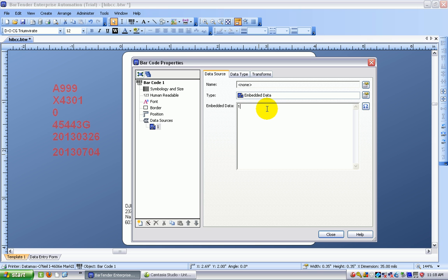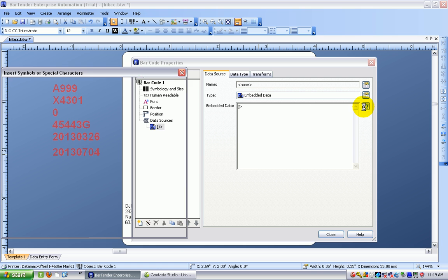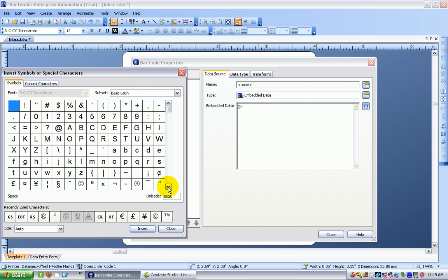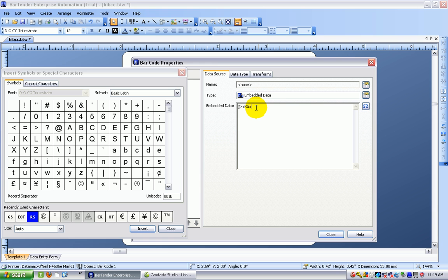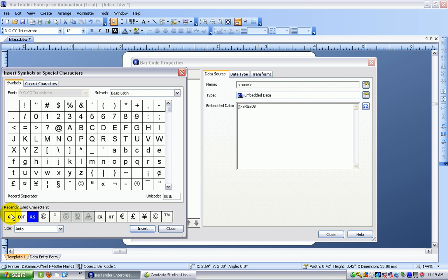The first thing I need to do is to add the message header, which is the open bracket, close parentheses, greater than symbol. And that's followed by the ASCII record separator. I have to click on this little symbol logo here. And in a couple of seconds I can choose my record separator and insert it into here. I'm just working my way through the specification that next asks for 06 as the format number followed by the group separator. And that's going to go in here.